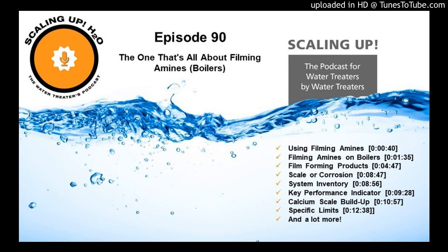So now I'm an old school water treater. I'm used to treating boilers and having multiple parameters that I can identify to see if the program is going properly. An example is like the one you gave. I can check for sulfite. I can check for my phosphate. I can check for the amine and the steam line treatment. I can check for how much polymer if I want to run that. So I've got all these different checks that I can run because I'm putting all these different products in.